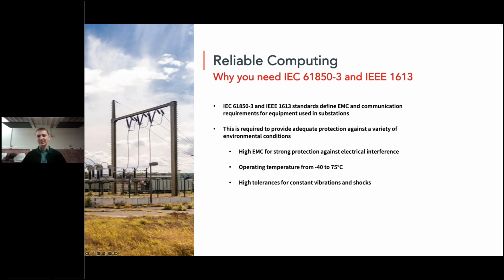For this, we have standards defined in 61850, especially IEC 61850-3, and in addition the IEEE 1613 standards. Those standards define not only requirements for environments, but also how systems can operate, how communication should work, and how reliable communication of equipment should be in substations. So we're talking about hardware specifications and how devices can withstand different environmental conditions.